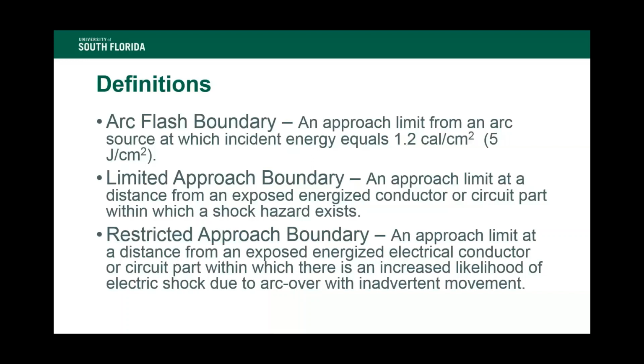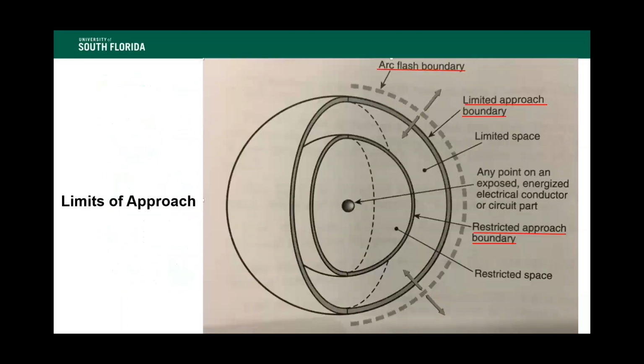Limited approach boundary is the limit at a distance from an exposed energized conductor or circuit part that can be approached. This is really in terms of protecting someone from electrical shock hazards. We don't want to let an unqualified person get too close to a potential electrical shock source. Likewise, restricted approach boundary is an approach limit at a distance from an exposed energized electrical conductor where there's an increased likelihood of electric shock due to an arc over with inadvertent movement. In other words, you get too close and maybe you bump your arm or you get startled and you accidentally come into contact with an energized component. Again, this is more of an electrical shock hazard boundary.